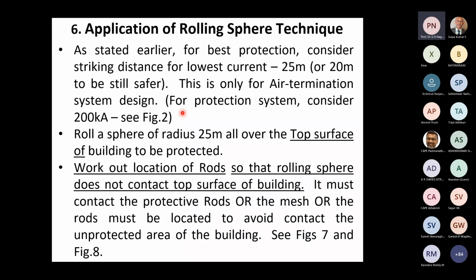But here it is the protection of the external surface of the building. Now, as we said, we will consider the best possible level of protection, considering 5 kiloamperes, for which the rolling sphere has a radius of 25 meters. So now roll a sphere of radius 25 meters all over the top surface of the building to be protected. Let me repeat, roll a sphere of radius 25 meters all over the top surface of the building to be protected. Why only the top surface? It's a very interesting question. If you have very tall buildings, much more than 60 meters, that means 200 feet, the lightning can hit the sides also, as we'll see a little later.